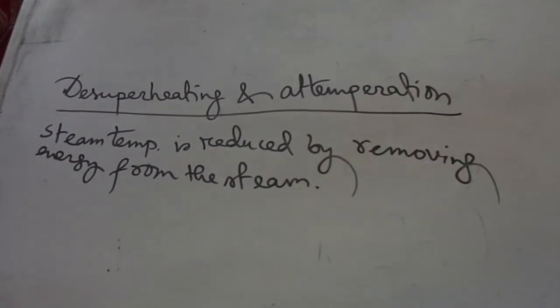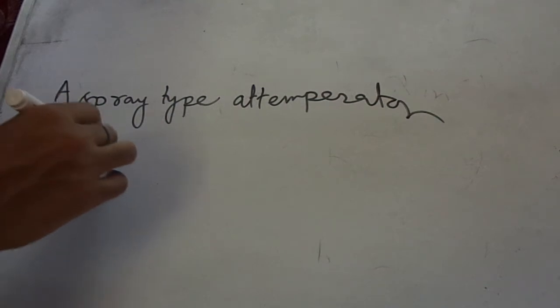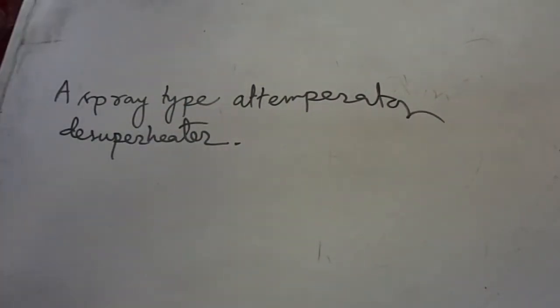A spray type attemperator is called a desuperheater. A spray type attemperator, called a desuperheater, reduces the steam temperature by spraying low temperature water from the boiler drum or economizer exit into the line between the primary and secondary superheaters or the radiant or pendant superheater. The spray nozzle injects water into the throat of a mixing venturi.